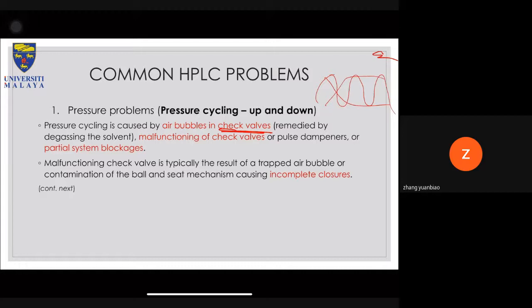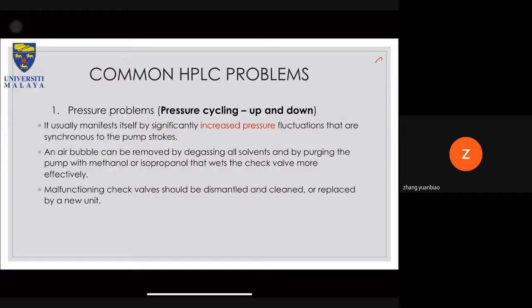A malfunctioning check valve is typically the result of trapped air bubbles or contamination of the ball and seat mechanism, causing incomplete closure. It usually manifests itself by significantly increased pressure fluctuations that are synchronous with the pump stroke. An air bubble can be removed by degassing all solvent or by purging the pump with methanol or isopropyl alcohol that wets the check valve more effectively. A malfunctioning check valve should be dismantled and cleaned or replaced with a new unit.